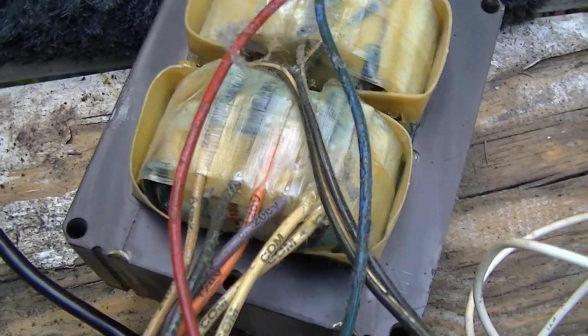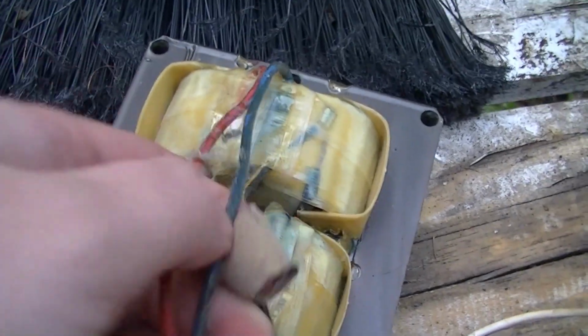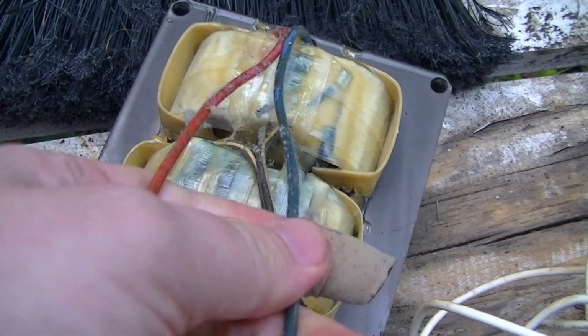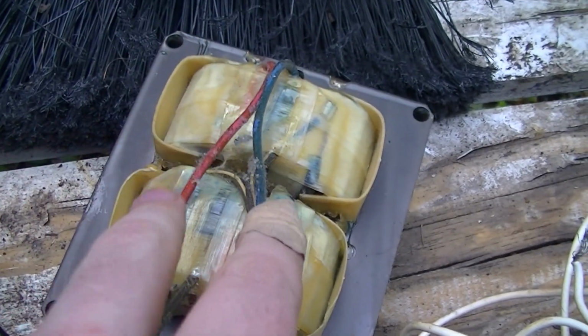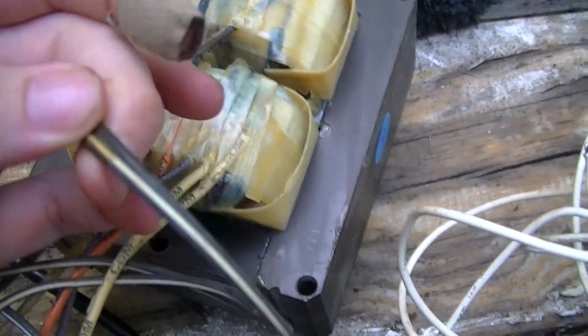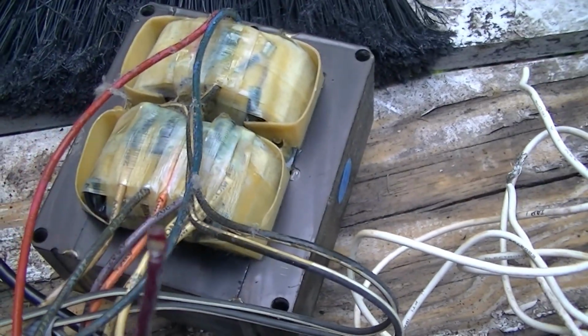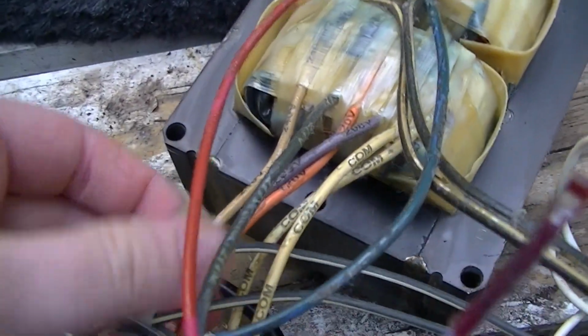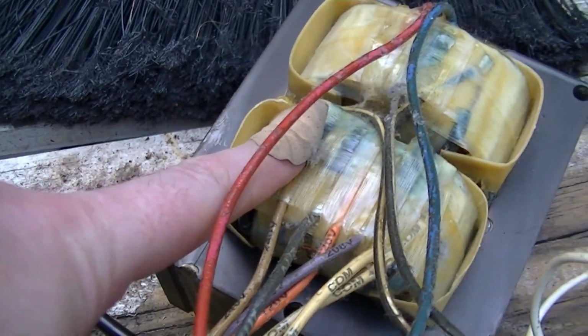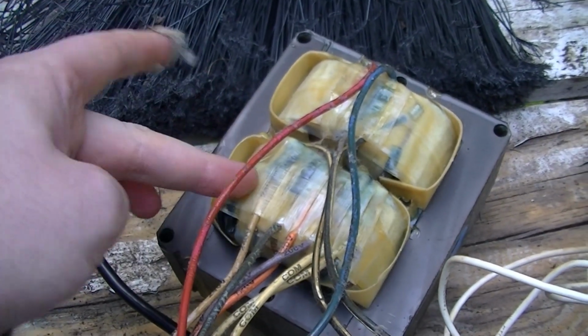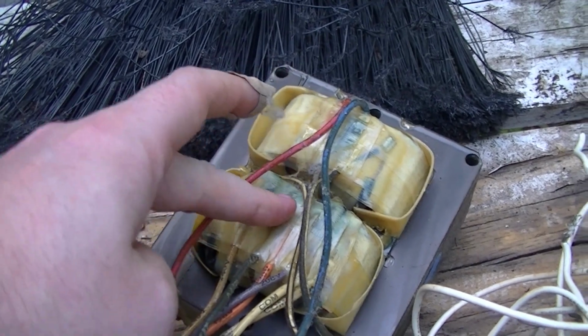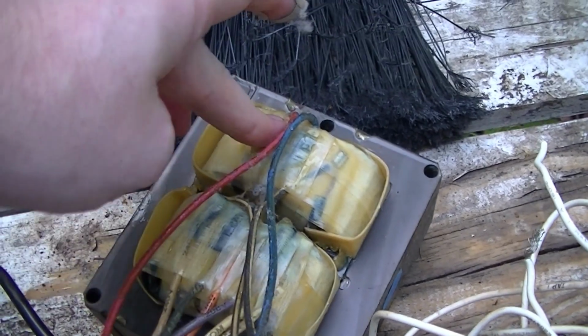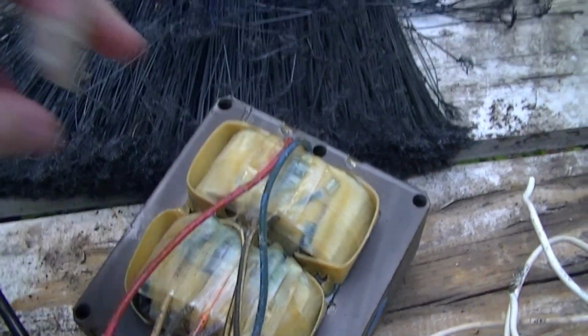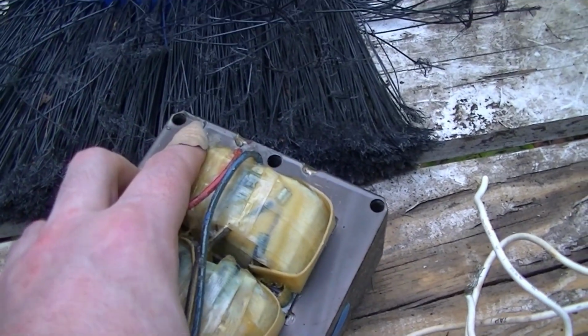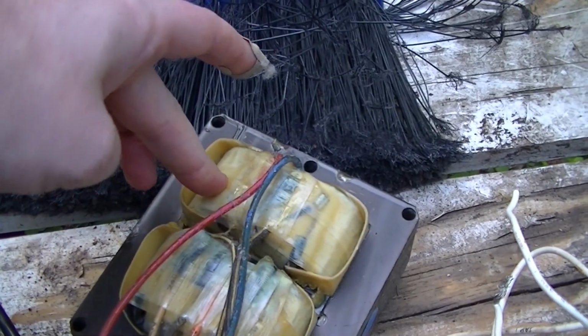And as an example of a ballast which is color coded, see these two wires which are what go out to the lamp, which is the red, the igniter, which is blue, that's quite common. These black with the white stripe wires, these are the wires that go to the capacitor, because this is a constant power auto transformer ballast. And then coming out of the auto transformer part of it, because the way that these ballasts work is there's an auto transformer which produces the needed open circuit potential for the choke part of the ballast, and then there's the actual choke. Although, of course, this being a constant power auto transformer ballast, this choke is used more for waveform forming, and the actual ballasting impedance is provided by the capacitor.